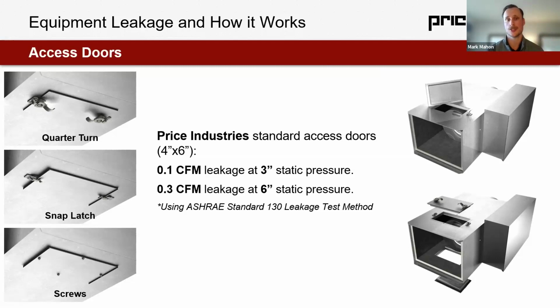So very low leakage. I would probably recommend for specification language that we should have less than 1% leakage at 3 inches of static pressure for an access door specification. That would be my recommendation, because that would give you competitive options from multiple manufacturers, and it would cover you for leakage. Of course, at Price, we could go more aggressive with that. This access door leakage is independent of casing size.